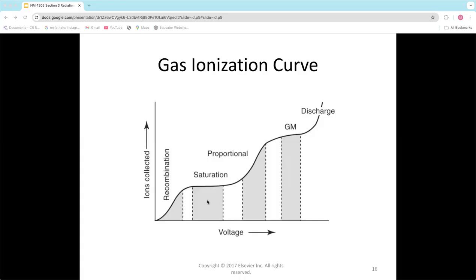Now, two things happen in the saturation region. One is that as long as it's detecting radiation, it will create more ion pairs the more radiation it sees. So you're going to get more current with more radiation, and it's going to give you a rise on your meter. The other thing is it's not just based on the amount, but also on the strength. If I'm detecting Tc-99m coming in at 140 keV, or I-131 at 364, because of the strength of the photons, that's going to give a different amount of ionization. So I-131 will ionize more than Tc-99m will.